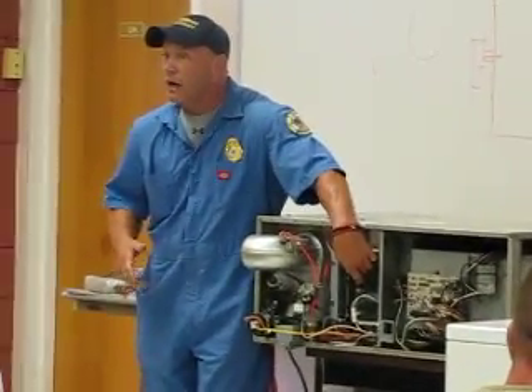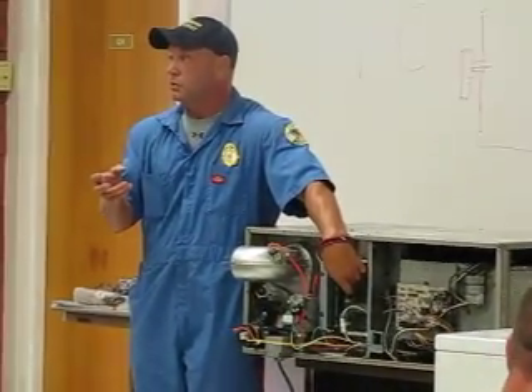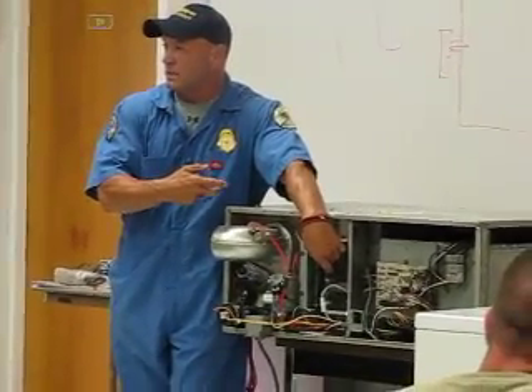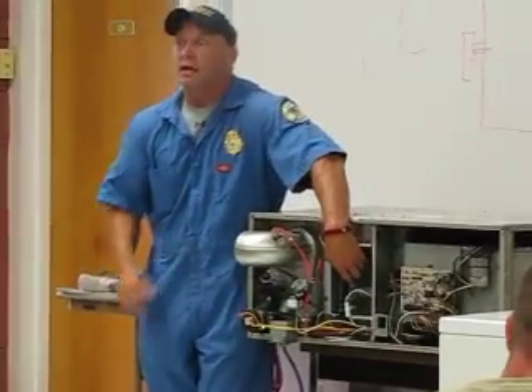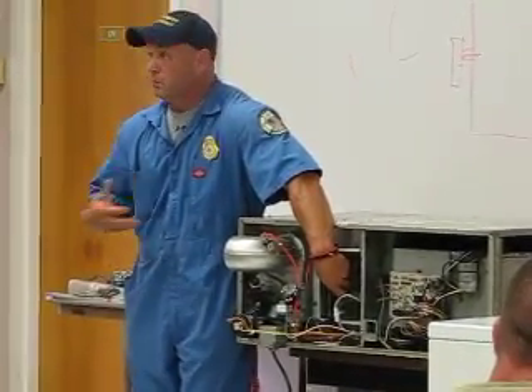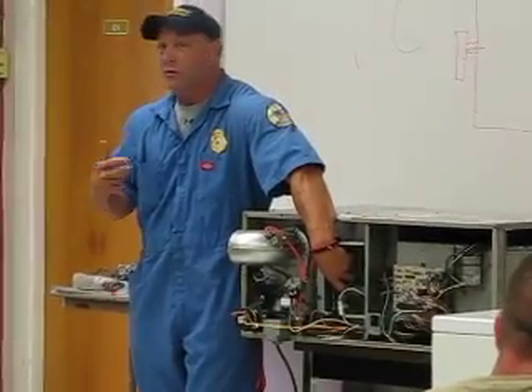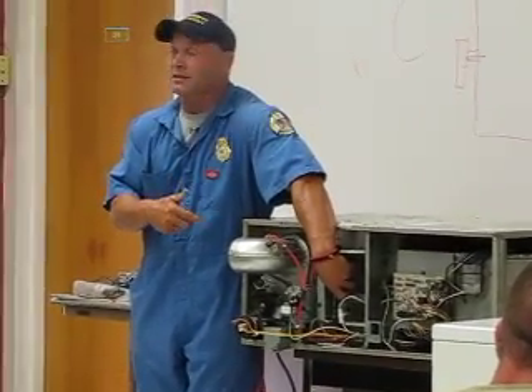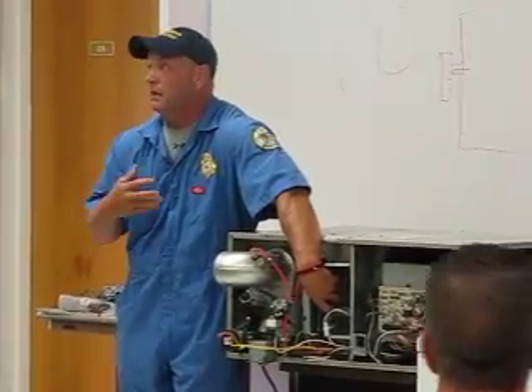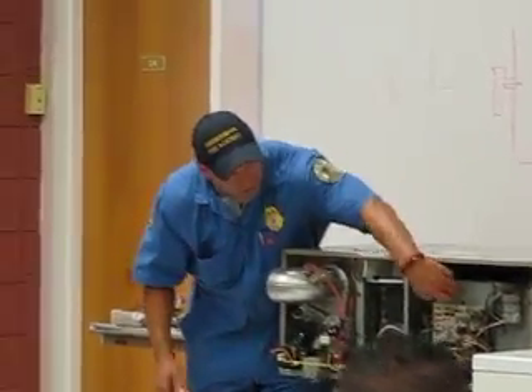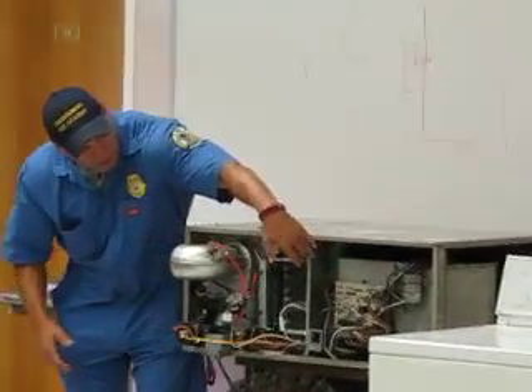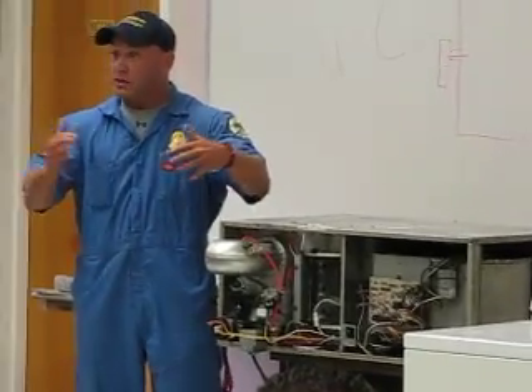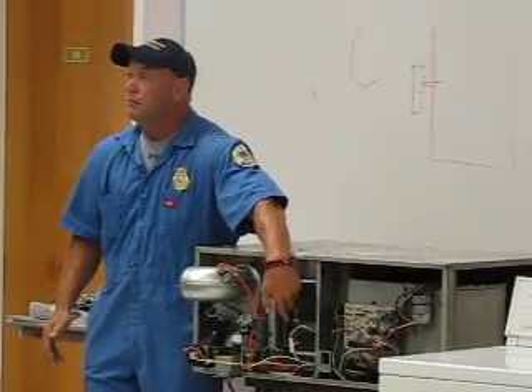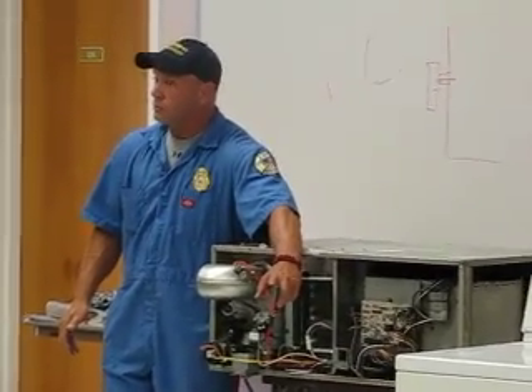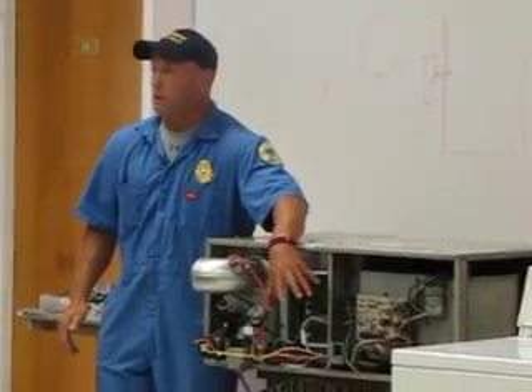This is the orifice right up under my finger. Each one of these is that orifice valve, and it's controlled, but right there is the fuel-air mixture. And so as it's going into this system, the fuel-air mixture is right, and now it just combusts inside the chamber. And once it's burning inside the chamber, it's no problem. However, when the chamber becomes damaged through oxidation or through just a period of time of expanding and contracting, now when the fan blows on it, which is down here under this control board, the fan blows up through, around the exchangers, into those cracks and pushes that gas back out. And that's when we have problems. That's when these furnaces catch on fire.